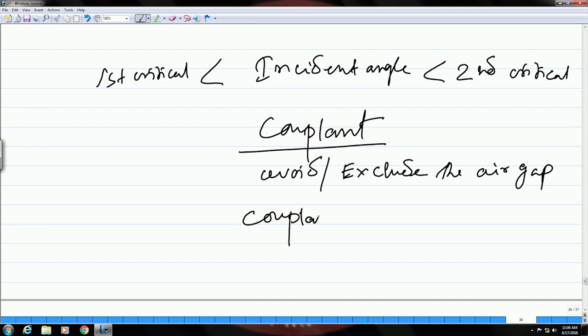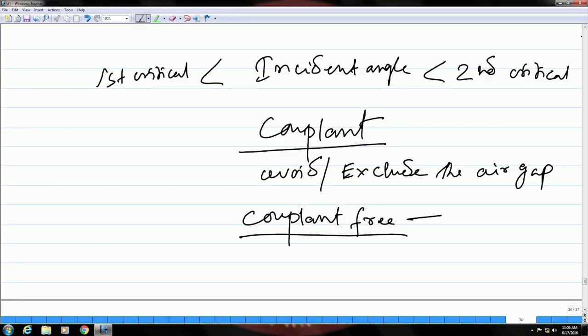If you want to do a couplant free test, then this electroacoustic transducer cannot be used, because in that case you have to touch it on the surface, and once you touch it on the surface, you need to ensure that at that interface there is no air gap, and you have to use a couplant. Okay. In order to do a couplant free test, you need to use a transducer which operates differently and which does not have to be in contact with the sample, like how the normal ultrasonic transducers are.